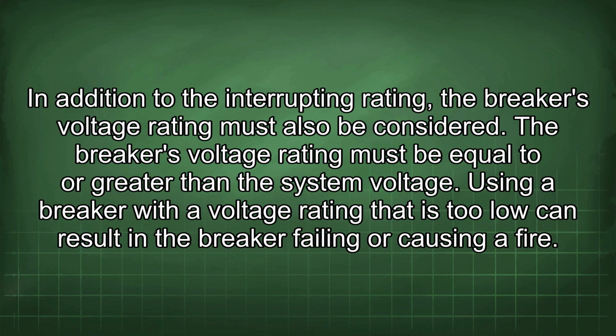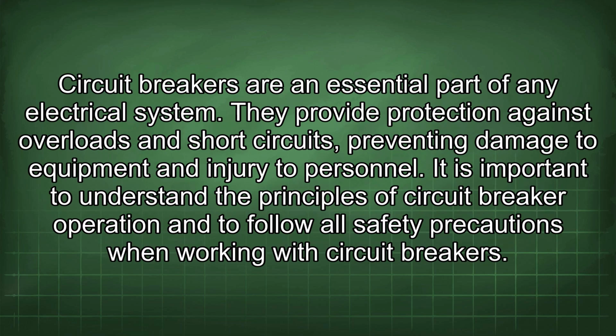In addition to the interrupting rating, the breaker's voltage rating must also be considered. The breaker's voltage rating must be equal to or greater than the system voltage. Using a breaker with a voltage rating that is too low can result in the breaker failing or causing a fire. Circuit breakers are an essential part of any electrical system. They provide protection against overloads and short circuits, preventing damage to equipment and injury to personnel.